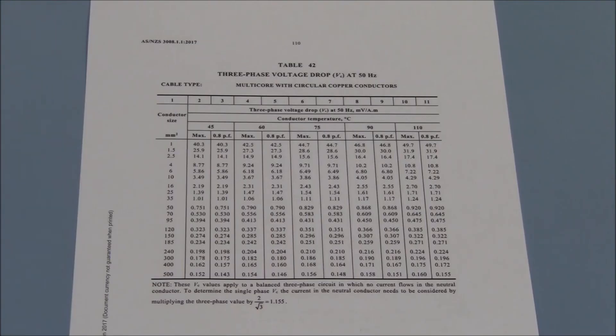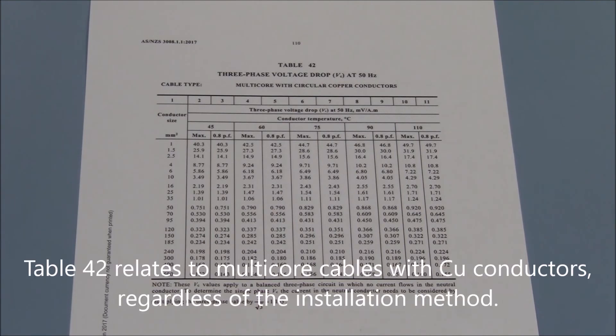We will use the same equation and find the value of VC in table 42 which relates to multi-core cables with copper conductors regardless of the installation method.